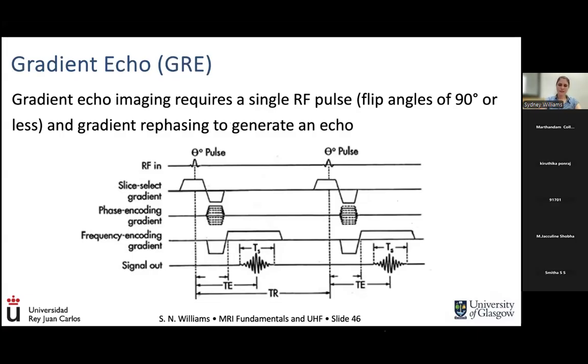MRI physicists love looking at these pulse sequence diagrams and coming up with clever new ones, but really there's two main types of pulse sequences that are really critical for MRI. The first one is the gradient echo, and this is a really simple way of showing a gradient echo. It's the same figure as before. Basically, it requires just a single pulse for a radio frequency field. The flip angle, so the amount that you actually move the spins towards the transverse orthogonal plane, is going to be up to 90 degrees. And then we're going to use gradients to time exactly when we want to collect the data at that echo. So basically, every TR only has one RF pulse and one time for collecting data.